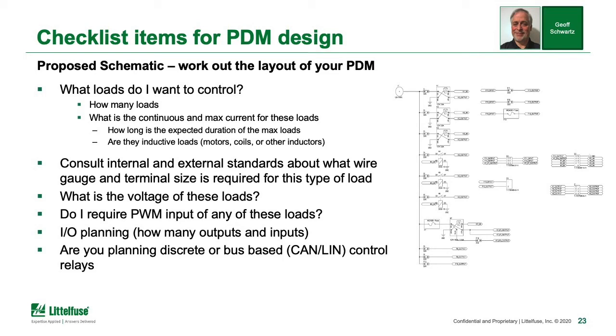What's the voltage of my loads? I need to understand that. Do I require PWM for any of these loads? That's important because it may mean incorporating solid state relays into the PDM, which drives the design in a certain direction. IO planning: understand your inputs and outputs. Am I going with CAN or LIN to control my relays? These choices drive your IO count, because without a bus system you need individual control circuits for all relay coils. So your IO, loads, voltage, communications, and external standards for wire and terminal sizing are all important.